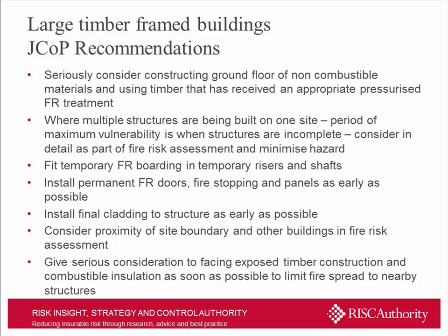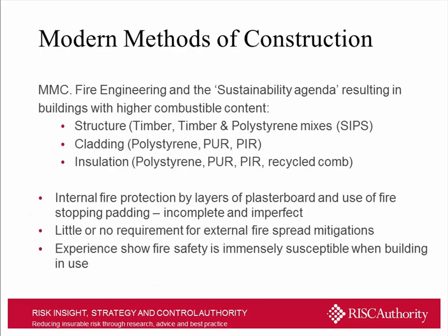We've been referred to a number of projects where the HSE have criticised the design and have called into question the suitability of the construction materials and construction method, and we've had to go in and support the contractor in doing the risk assessment work that's required, and providing them with some guidance as to the approach that they can take to minimise fire risk, and should they wish to continue to use timber frame as their preferred method of construction.